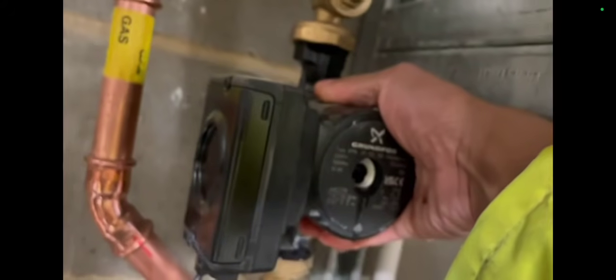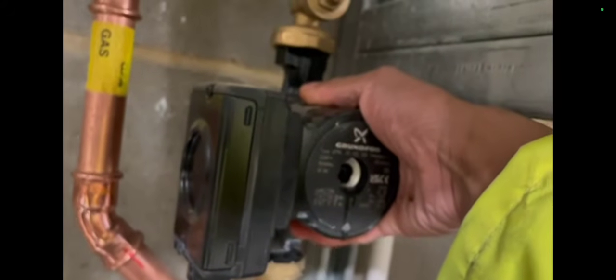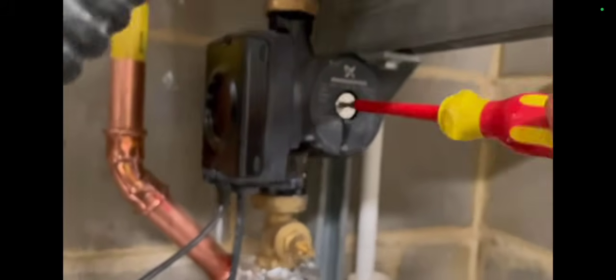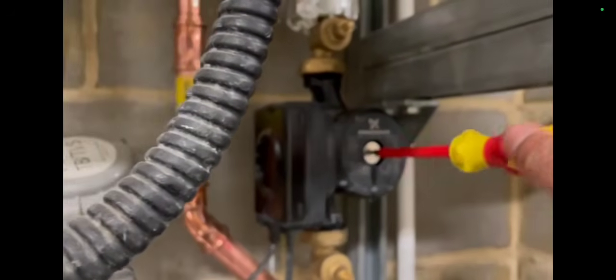I mean, I could have gone as far as taking the pump off and having a look inside, but it looked like it was operating well. I could have also checked the amps on it, like I said before, to see if it was in line with what the manufacturers state. I could have also got my clip-on thermometers to check the circulation throughout the boiler, the flow and return and so on, as it can be more accurate.